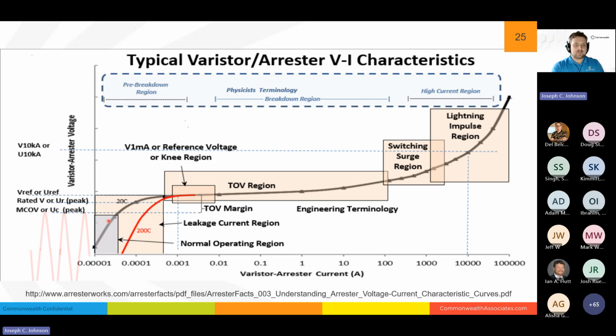And then as you start seeing the rise in voltage, you hit this knee point where a very small amount of increase in voltage is an orders of magnitude increase in current. I mean, from just this small increase here in voltage goes from 0.001 amps to 10 amps. And this is your TOV region that we were talking about before. These curves are not necessarily fit to look at long-term discharge levels. These are more of a fast event. So this isn't necessarily behavior for seconds, but it does show an instantaneous behavior of the arrestor.